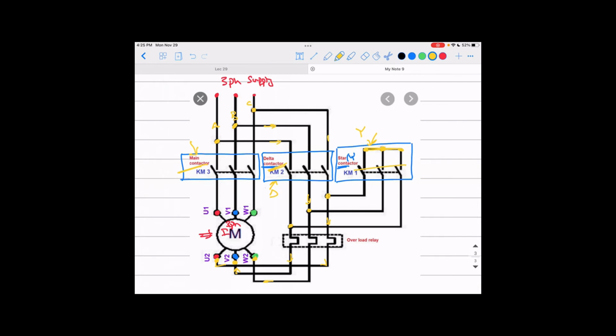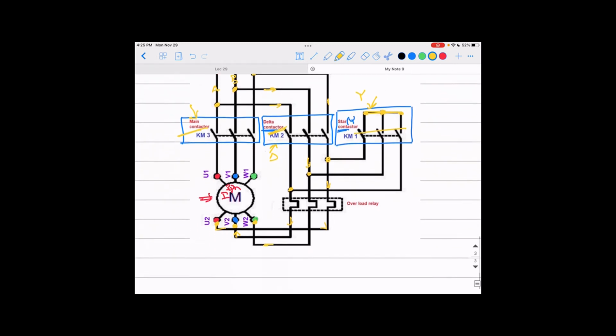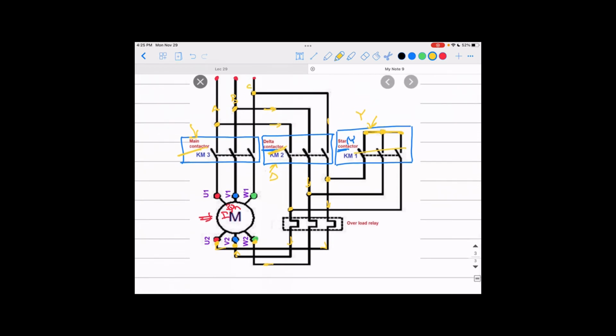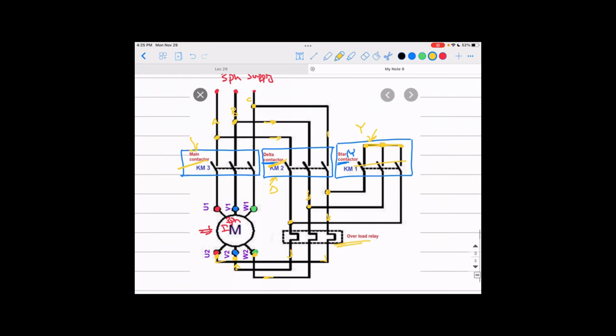So that is basically how you can go with the connections for this machine. Okay? That is how we can switch from Y connection to delta connection, or from delta connection to Y connection if we want to. And by the way, that's the overload relay, the same as we talked about before in our DOL. Okay, guys?